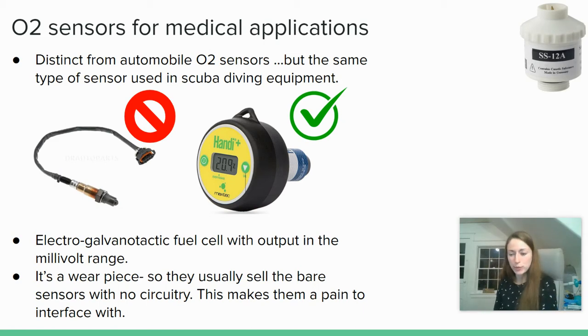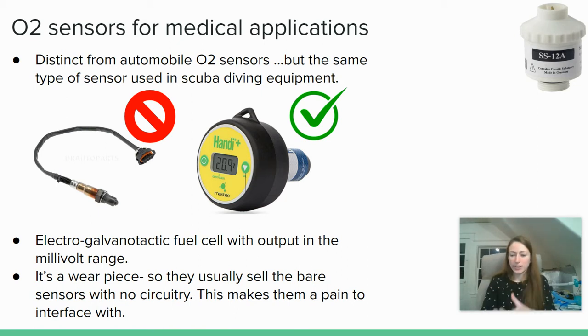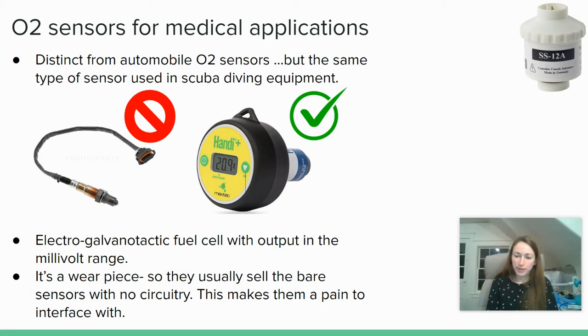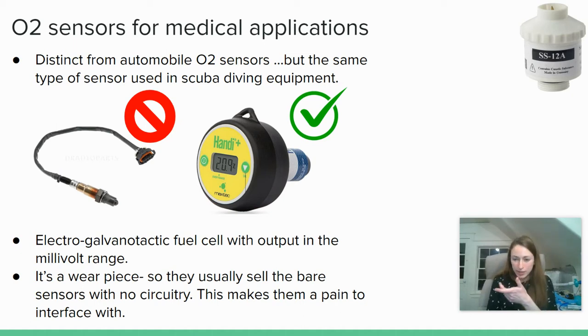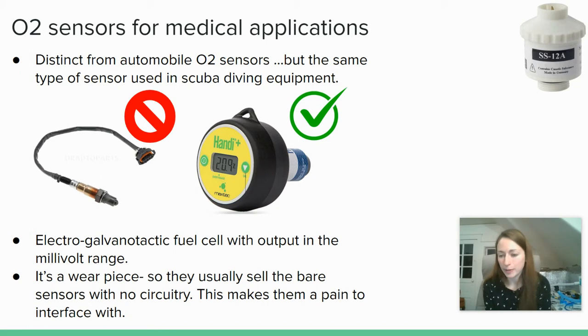The type of O2 sensor we'll be using is an electro-galvanic fuel cell, which gives output in the millivolt range — basically like a battery. You don't need to supply any current to get a reading; it's continuously outputting. When you order one of these O2 sensors, it comes in a little can. Because it is continuously operating, that makes it a wear piece, so it comes with an operating lifespan on the data sheet. Since these are wear pieces, they're usually sold as raw sensors with no circuitry built in, which makes them a little more difficult to interface with, but easier to swap out as replacement parts.